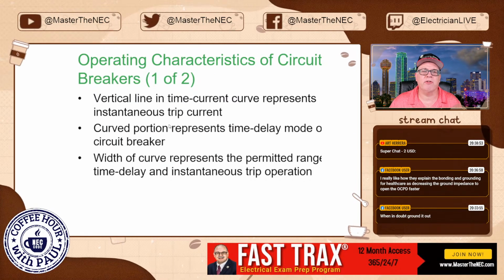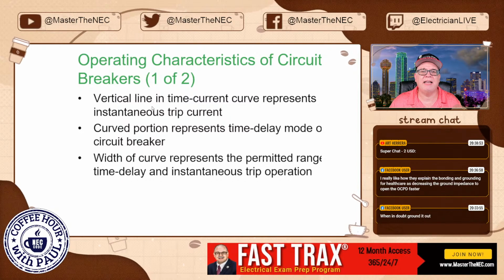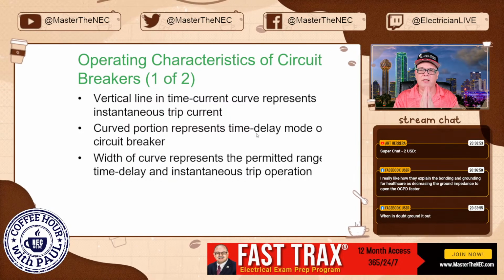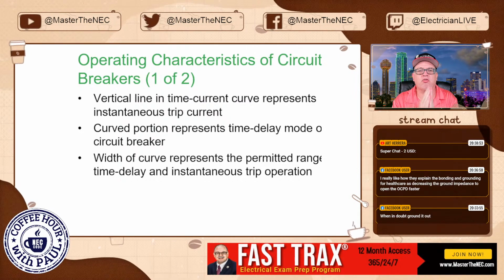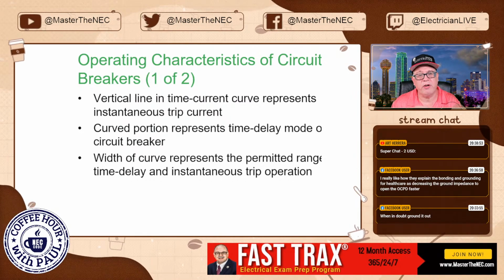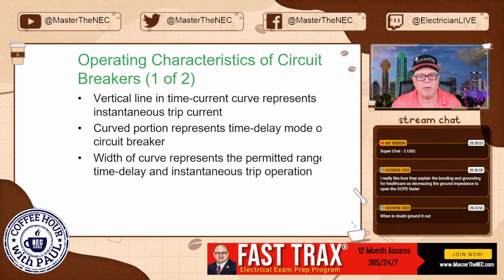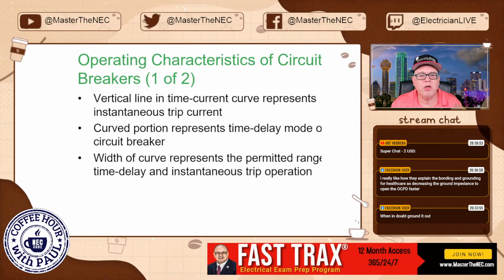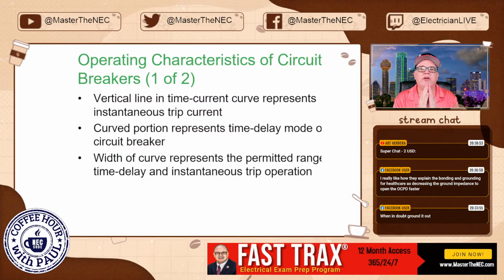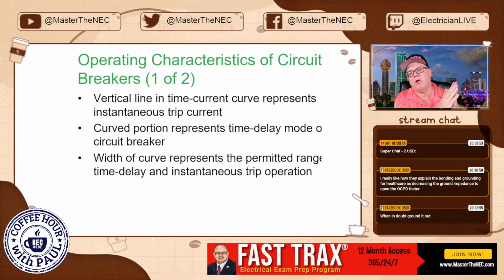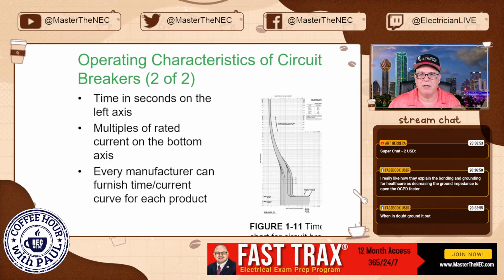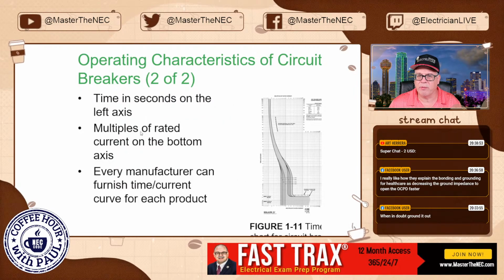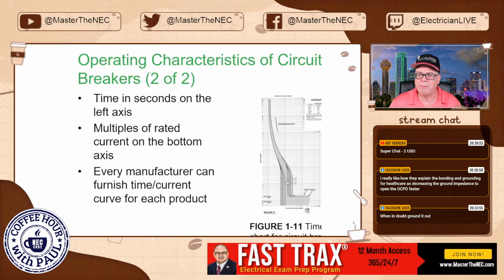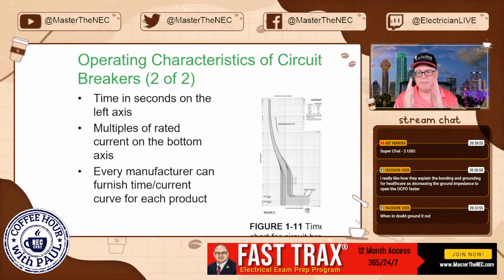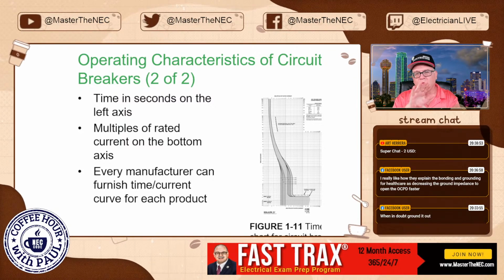All right, operating characteristics even more here. It says vertical line in the time curve. So the vertical line represents the instantaneous trip current. The curved portion represents the time delay mode of the circuit breaker, like what it's going to take to trip. And then the width of the curve represents the permitted range of the time delay as opposed to the instant trip operation. Okay? So when you start looking at, here we go, you've got the vertical line, the horizontal, and then you've got the spacing between where the instantaneous, then you have the time delay. All of that is when you're looking at and overlaying trip curves.